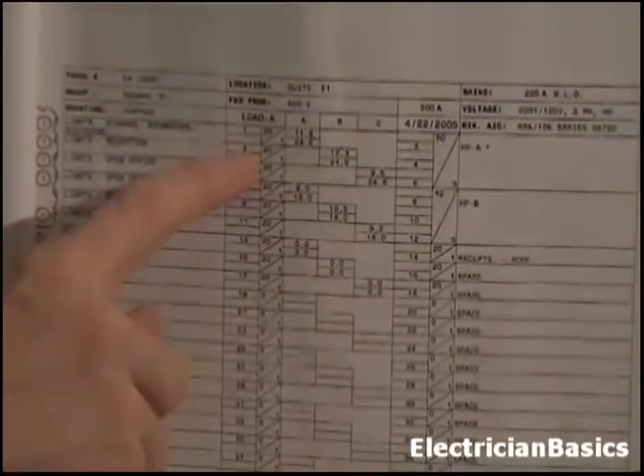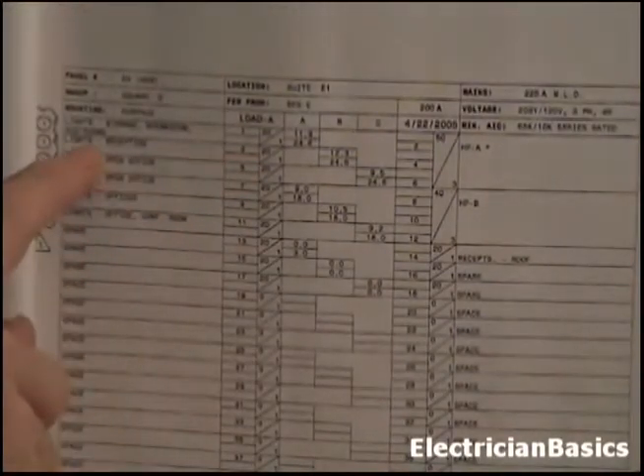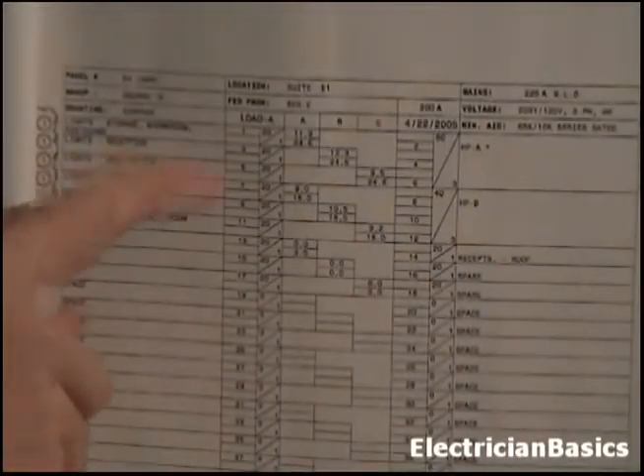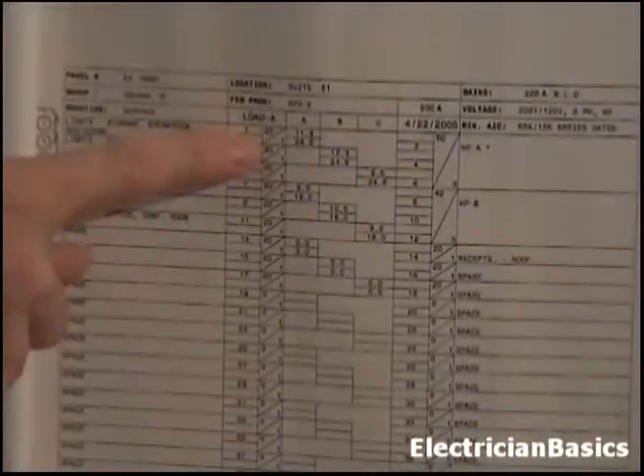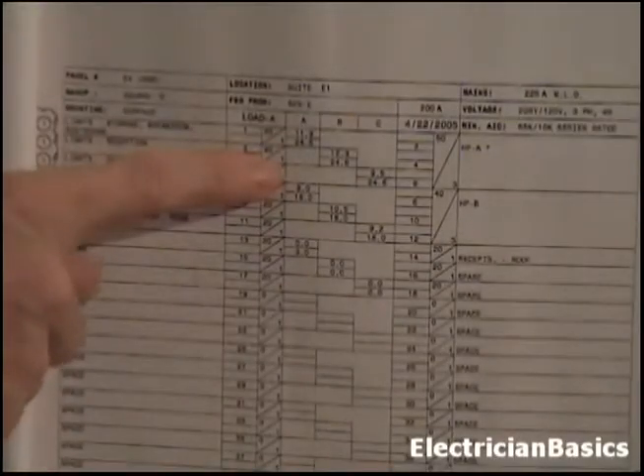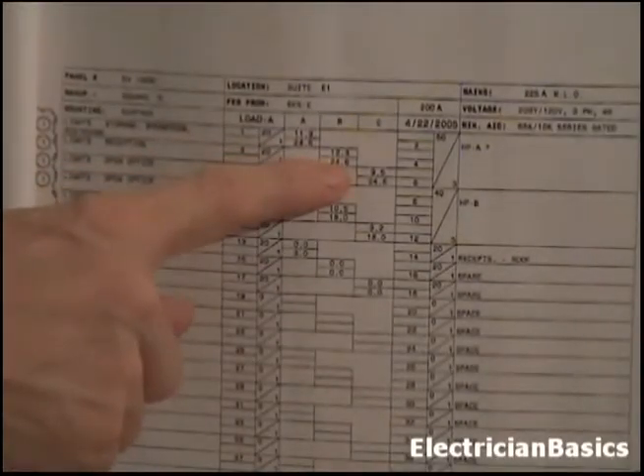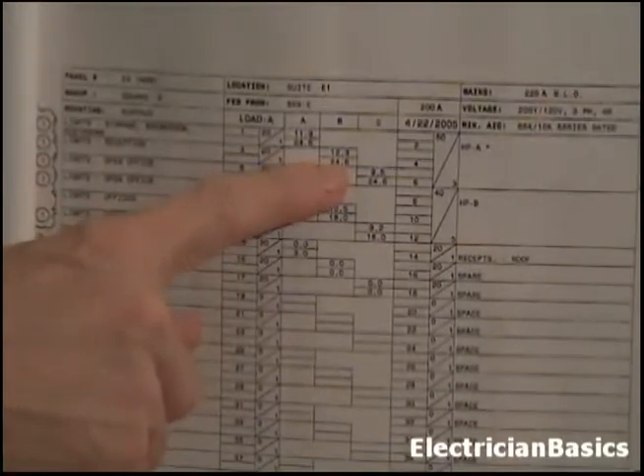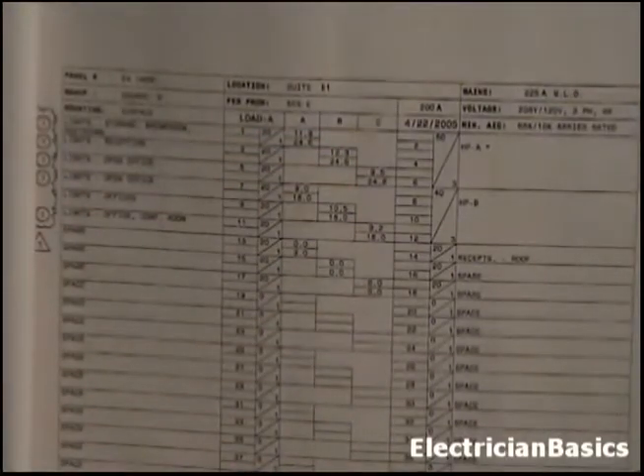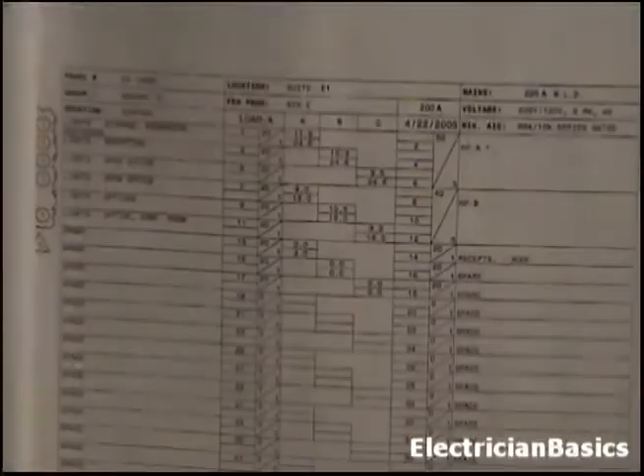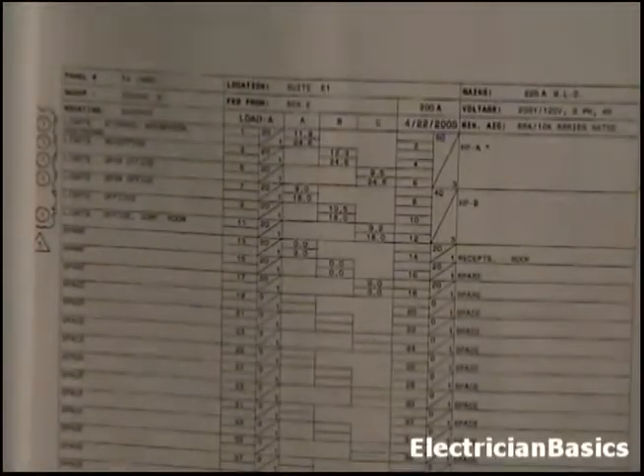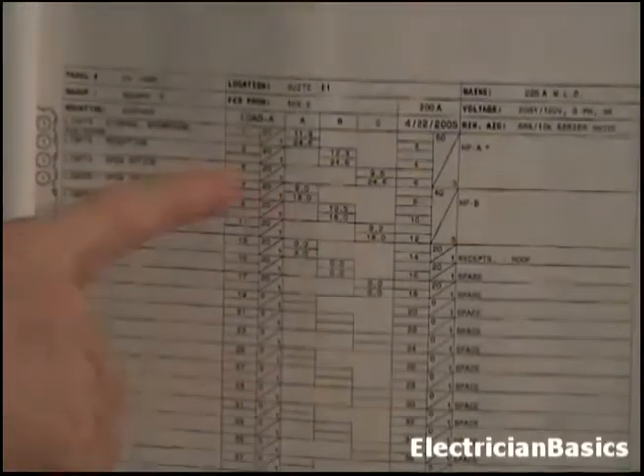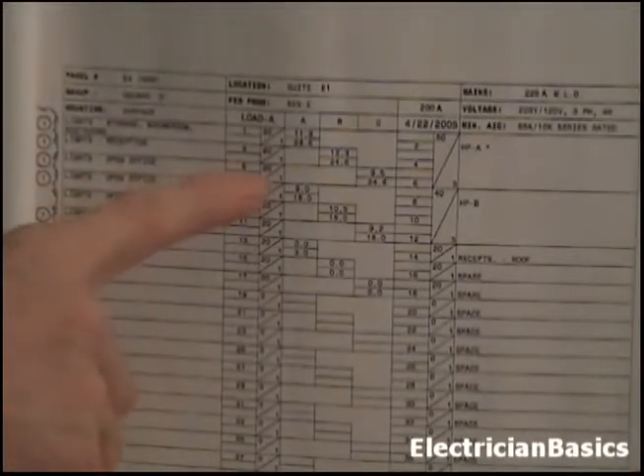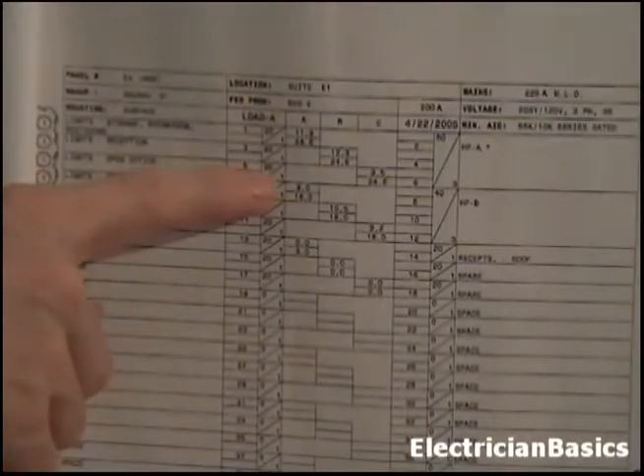Circuit 3, okay, is the lights in the reception area. It's a 20 amp breaker, and it's a single pole breaker. Now it's on B, so we find over here where this is information we're giving the continuous and non-continuous load and things like that. And that's a little bit beyond the scope of this lesson right now. And again, we can go circuit 5. Okay, lights, open office, 20 amp breaker, it's a single pole breaker, and that's phase C.